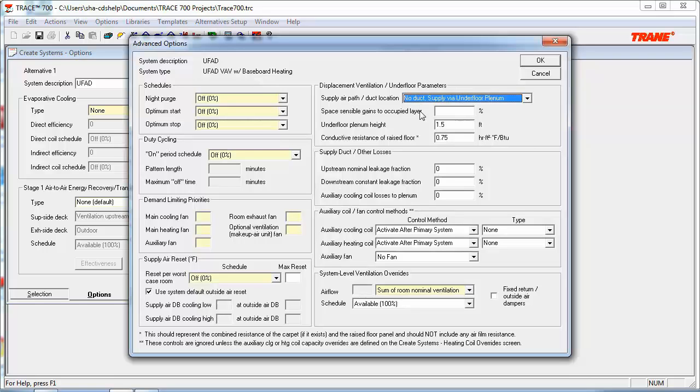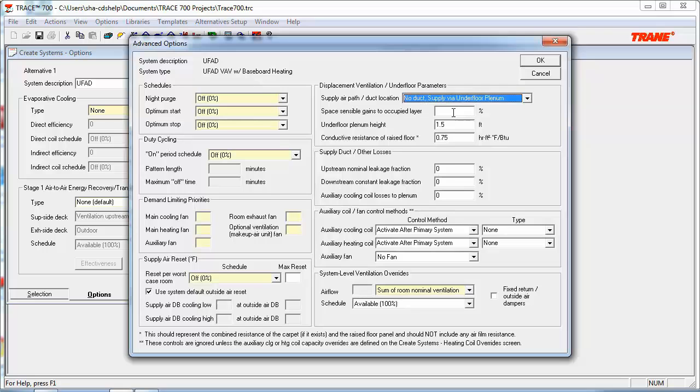For some additional considerations, we can also input an underfloor plenum height here, which is defaulted at 1.5 feet. And you can also change the conductive resistance of the raised floor, which this is an R value, not a U value. The last input here is the space sensible gains to the occupied layer. Since this is a UFAD system, you can either let TRACE calculate how much load is going into the occupied layer, as described from the calculation methodology, or you can input a value that is calculated outside the program.